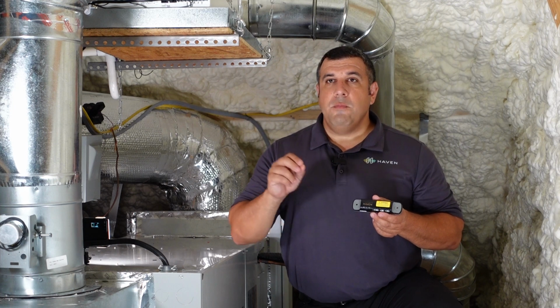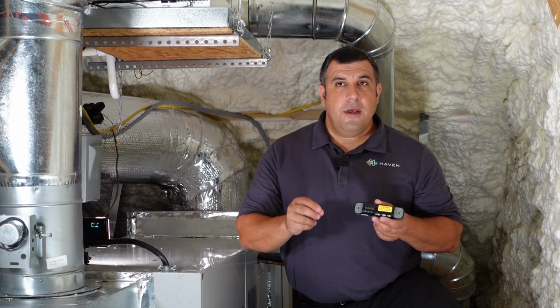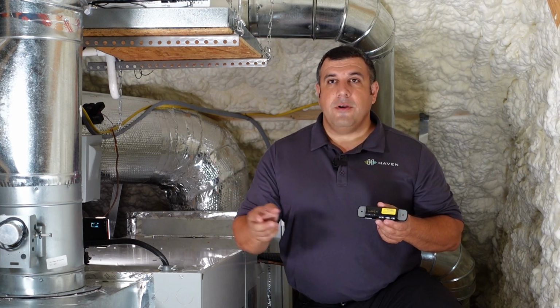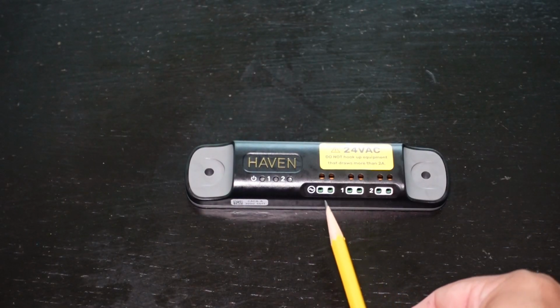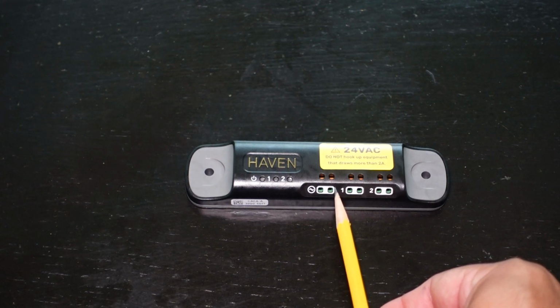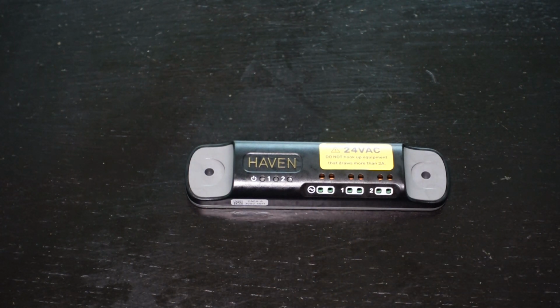If you would like to switch more than 30 volts at 2 amps, you can implement a pilot relay circuit at your own discretion. The leftmost terminals on the controller are for power. Connect to the R and C terminals from the air handler control board or other transformer that you want to use, as long as it's between 9 and 30 volts AC or DC.